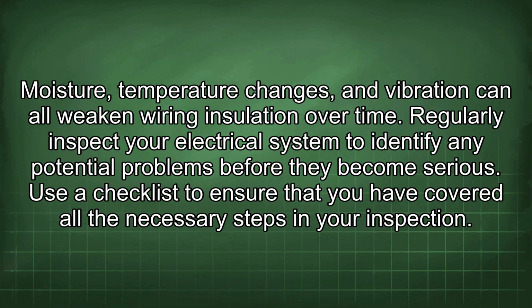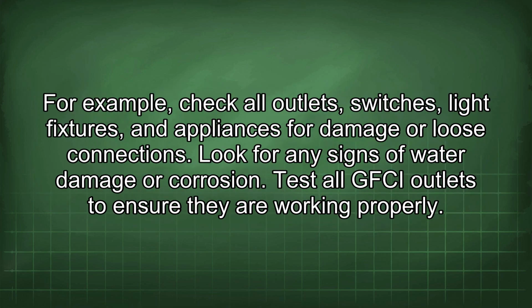Moisture, temperature changes, and vibration can all weaken wiring insulation over time. Regularly inspect your electrical system to identify any potential problems before they become serious. Use a checklist to ensure that you have covered all the necessary steps in your inspection. For example, check all outlets, switches, light fixtures, and appliances for damage or loose connections. Look for any signs of water damage or corrosion. Test all GFCI outlets to ensure they are working properly.